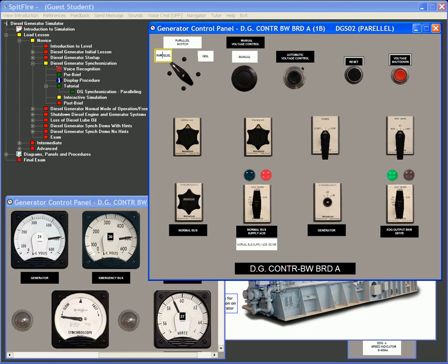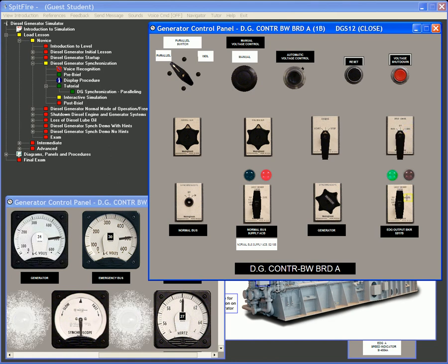The speed is slightly bumped on the speed control switch to get the diesel at 60 Hz on the meter at the bottom. The synchroscope is switched on and the lights flash as the engine speed is fine-tuned using the speed control switch. At 5 minutes before 12 o'clock, the breaker is closed and then the synchroscope is turned off to complete the required steps.